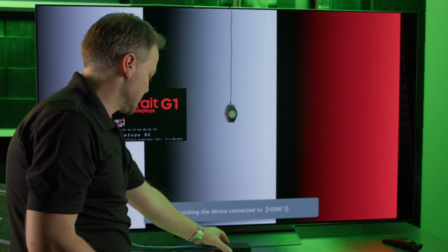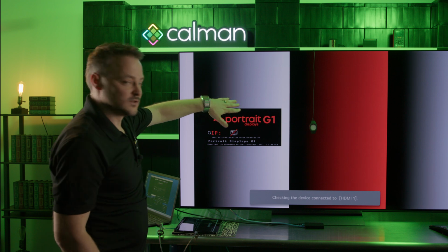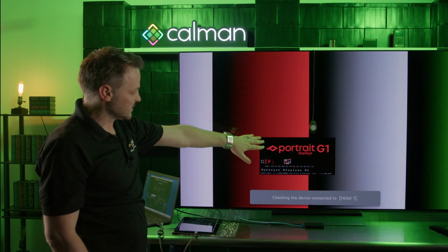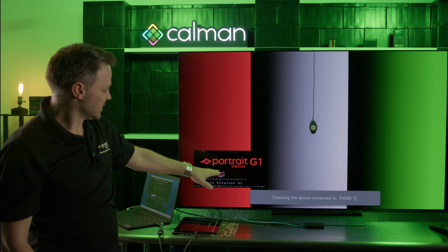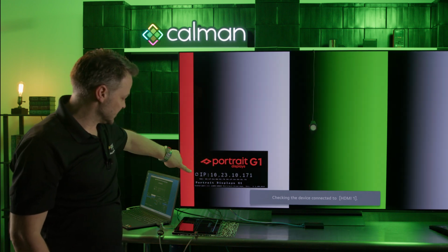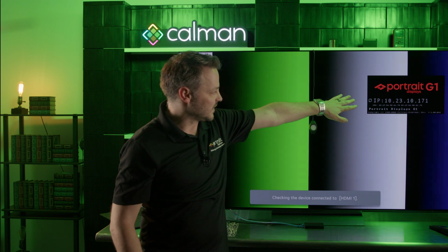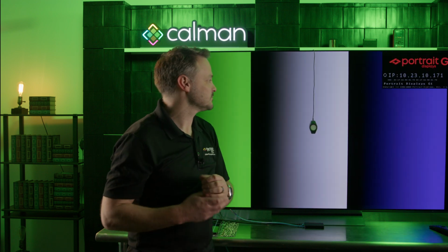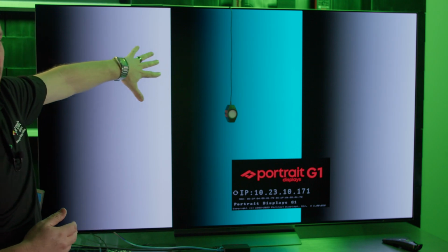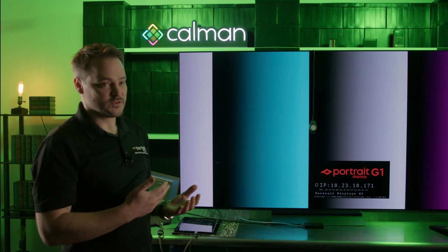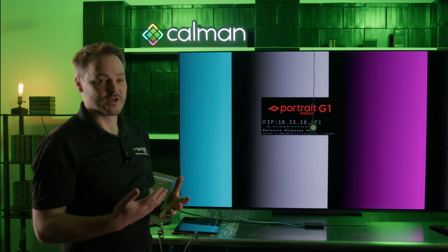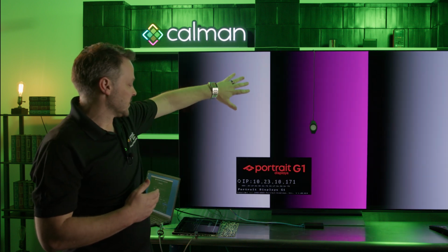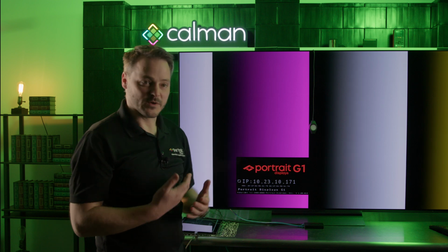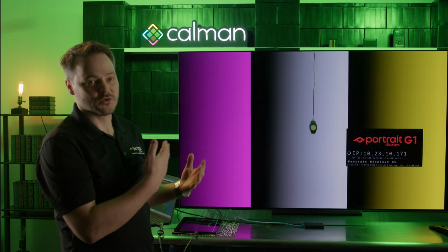You can see as I plug those in that we've now got a signal coming in on the screen. Once the generator has connected to the network, it's going to show an IP address right here. You can see it's syncing right now, and it does now show the IP address. A couple of things to talk about really quickly about this generator specifically, and about what you're seeing on the screen. You'll notice that everything on the screen is dynamic. The point there is that as soon as you plug in the generator, we're going to start warming up the screen, making sure that screen is ready for calibration. Next thing is we do show the IP address. That's how we're going to connect. We make sure that that's nice and prominent. You can see it on the screen right away.